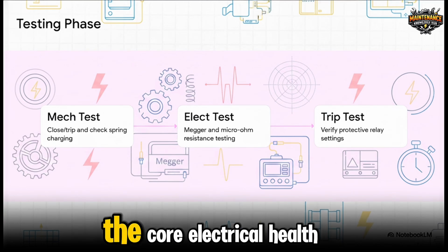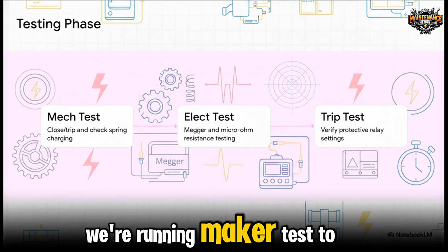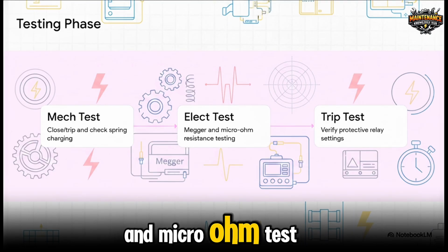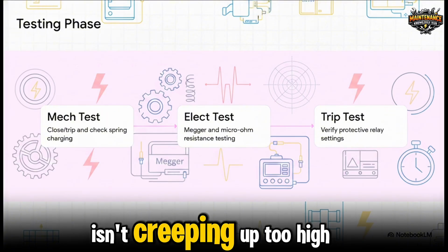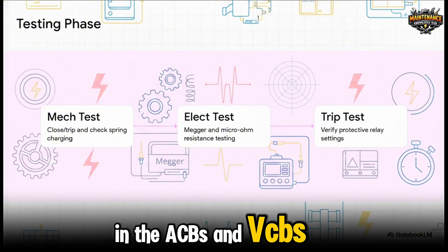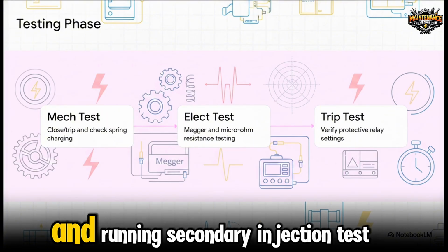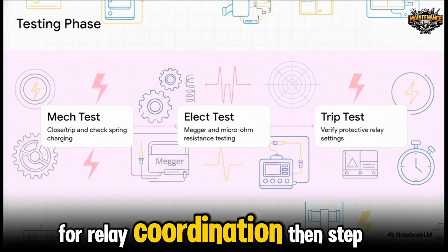Step 6 gets us into the core electrical health. We're running Megger tests to check the insulation and micro-ohm tests to make sure contact resistance isn't creeping up too high in the ACBs and VCBs. You're also checking trip coils and running secondary injection tests for relay coordination.